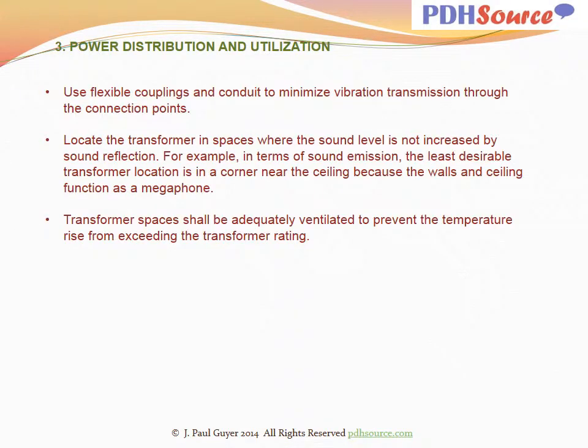Use flexible couplings and conduit to minimize vibration transmission through the connection points. Locate the transformer in spaces where the sound level is not increased by sound reflection. For example, in terms of sound emission, the least desirable transformer location is in a corner near the ceiling because the walls and ceiling function as a megaphone. Transformer spaces shall be adequately ventilated to prevent the temperature rise from exceeding the transformer rating.